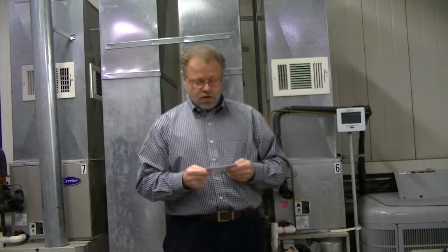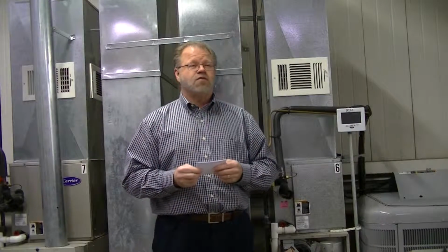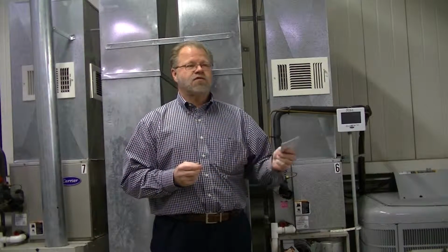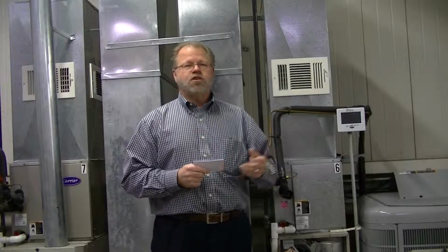One of the biggest reasons why heating and cooling systems don't operate is a clogged or dirty filter. According to an ASHRAE Journal article in October 2012, John Proctor states that the static pressure increase from a dirty filter not only reduces efficiency, but lowers the capacity.